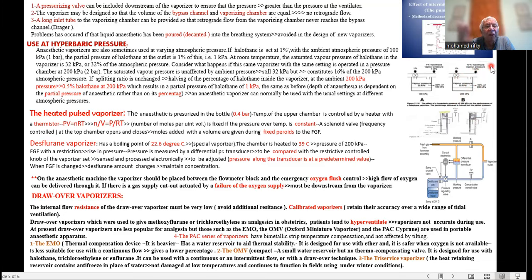So whatever the pressure, the partial pressure of the anesthetic released from the vaporizer, whether in a normal atmosphere or high or low atmosphere, will be similar. So no need for adjustment, apart from this desflurane vaporizer, we must rearrange.